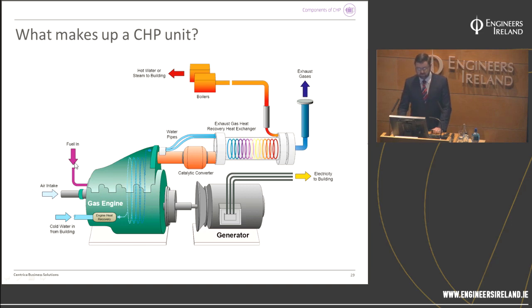If we follow the same flow again and look at the gases, you can see the exhaust gases pass through here. At this point they're at about 620 degrees. By the time they exchange heat with the water in the shell and tube heat exchanger here, they're coming out at about 120 degrees.